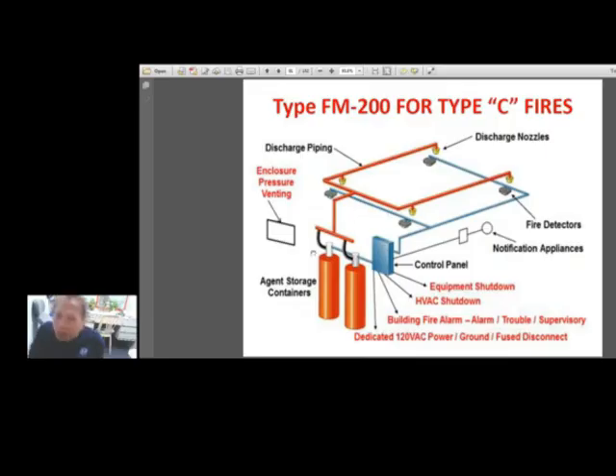And they would send a signal to your control panel, which would automatically allow the flow of the discharge of the agent. Okay. Enclosure pressure venting. There is also the equipment shutdown, HVAC shutdown, building fire alarm, and dedicated controls. Okay, so that's how this FM200 operates. Similar to Inergen also and Novec. Almost similar.